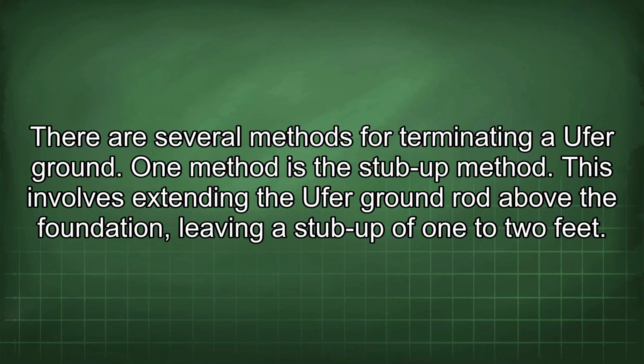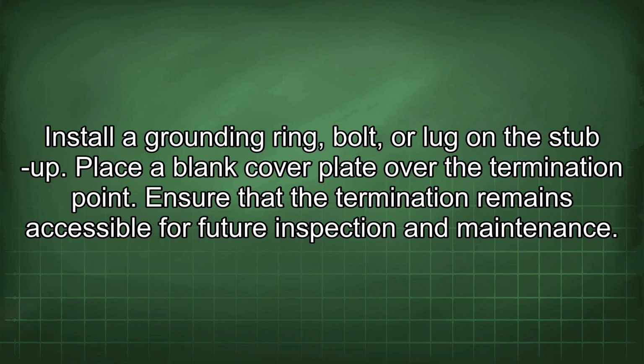There are several methods for terminating a Ufer ground. One method is the stub-up method. This involves extending the Ufer ground rod above the foundation, leaving a stub-up of 1 to 2 feet. Install a grounding ring, bolt, or lug on the stub-up. Place a blank cover plate over the termination point. Ensure that the termination remains accessible for future inspection and maintenance.